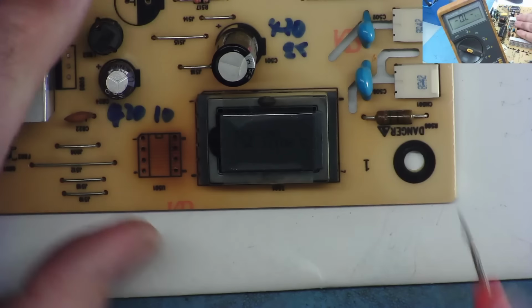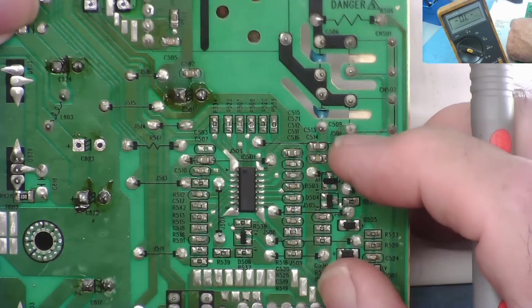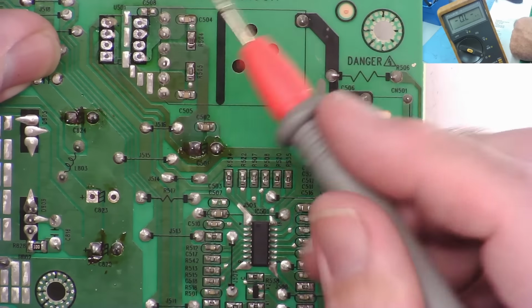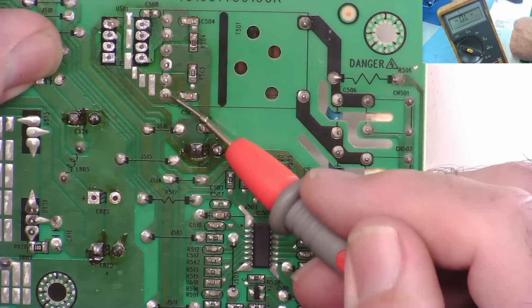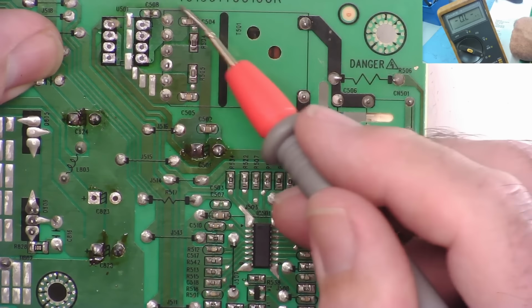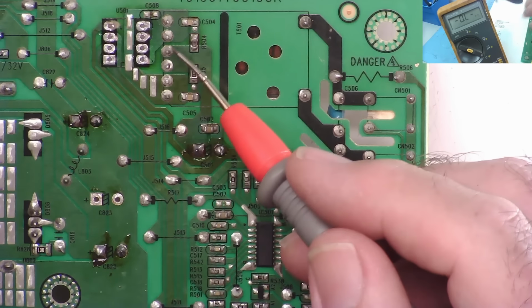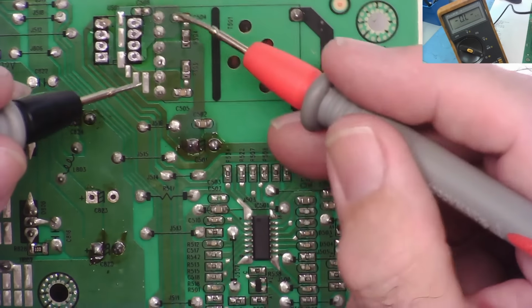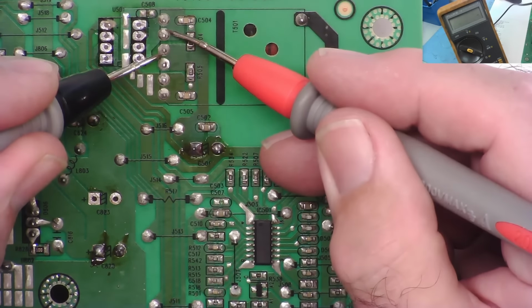The actual transformer in the inverter - we might be able to prove that before we go looking for parts. This is the inverter transformer, and you can see we have effectively 3 terminals here, so these are two and two. You can see they've got wide traces connected together, and this will probably read basically like a short circuit because the windings will be a low resistance.